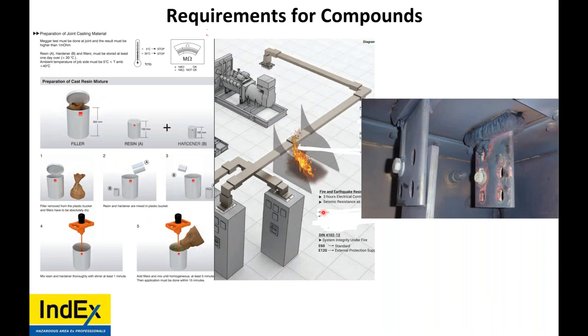Now, on the end, inside the transformer, you'll find the terminations. Now, this box is Ex e. Unfortunately, somebody ran this one for 4 months with only one bolt on the flexible bus links, and then it blew up. So the problem is, when it blew up, this entire section had to be replaced. You're talking millions of dollars.